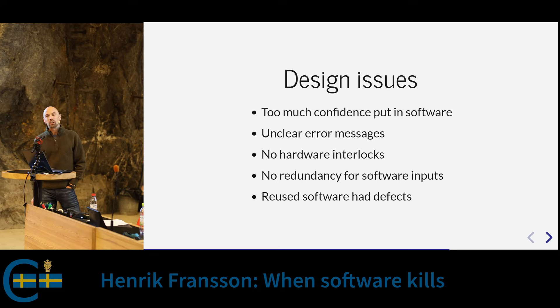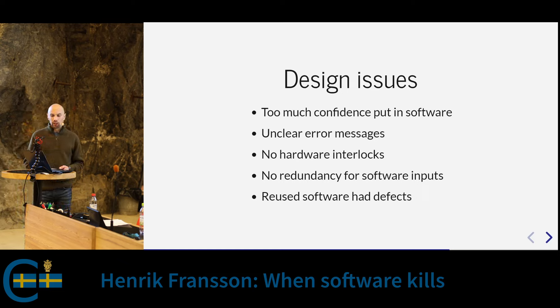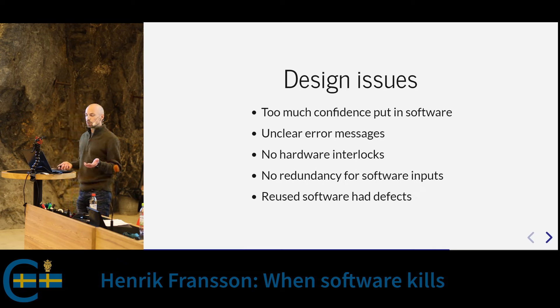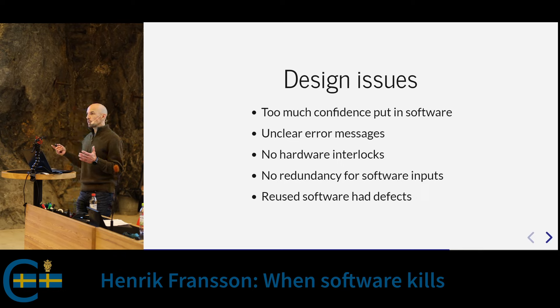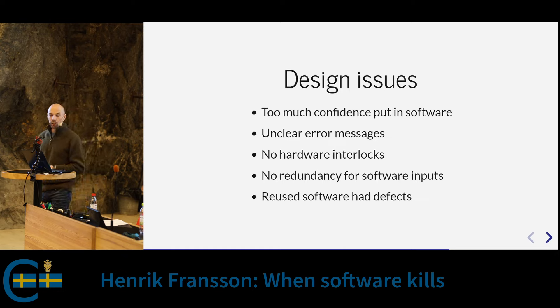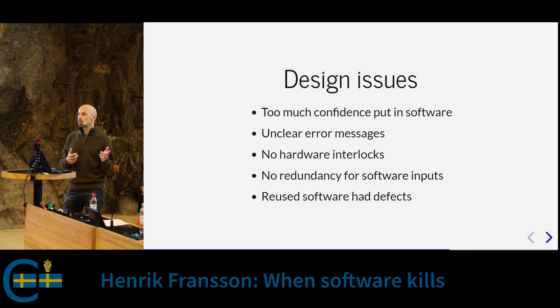There were also engineering design issues: all trust and all safety was placed in the software instead of using hardware. The error message 'Malfunction 54' tells you nothing. There were no hardware interlocks as existed on previous models, no secondary independent sensors to verify position — only the microswitch inputs. And critically, they assumed the software was safe because the previous machines had been in the market for years without this problem, concluding the software must be bug-free.